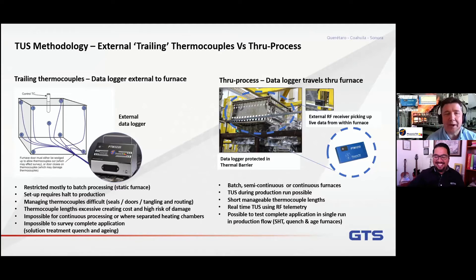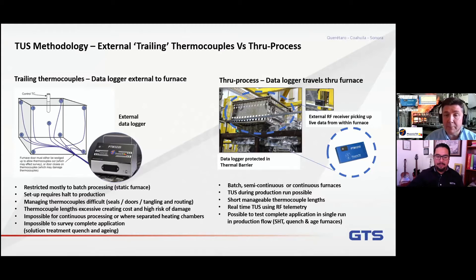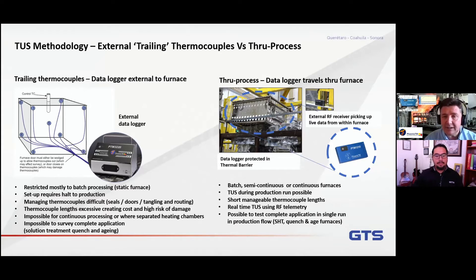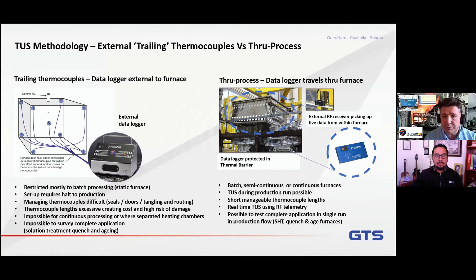The traditional way of doing a survey is generally with an external data logger outside of the furnace. Particularly if it's a batch process, that's probably the most economic and efficient way of doing it, and it's been the methodology applied for many years. But in some unique situations, particularly where there's product movement — such as the aluminum solution heat treatment, generally a semi-continuous or continuous process — a different approach is needed.